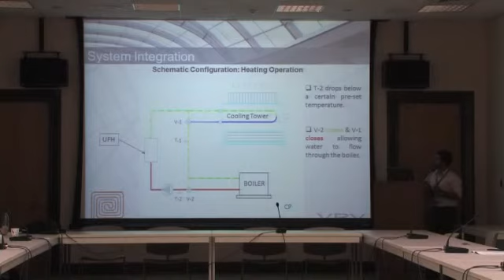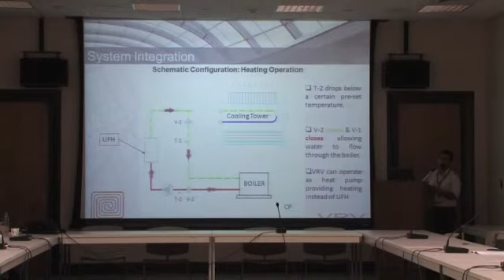And then in this scenario, the VRVs can operate in the cooling or heating mode as a heat pump, because we have a low return temperature. In the recovery operation, let's say during moderate climate conditions, some people with the southwest exposure will require cooling and the others will require heating. T1 and T2 will be set between a range of temperature, between 40 to 45 degrees. Both V1 and V2 will close, and heat dissipated, heat loss from the underfloor heating will be gained by the VRV. A self-sustaining system.